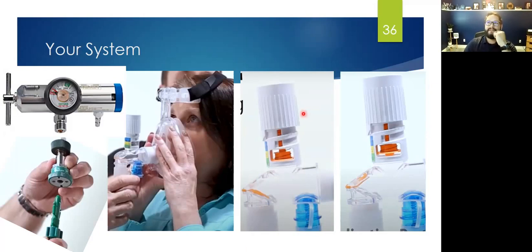So gang, then if you look at this next picture, here's a couple things I really want you to see, right? So this is going to tell you a few things on troubleshooting your system if there's an issue. So first and foremost, this is that anti-asphyxia valve I was talking about. And what happens is there's holes right here. And if there's no flow coming in, air and oxygen not flowing in, or not enough of it, that anti-asphyxia valve is going to drop down, and ambient air is going to come in so they can breathe and they don't asphyxiate. So, obviously that's key to look at.